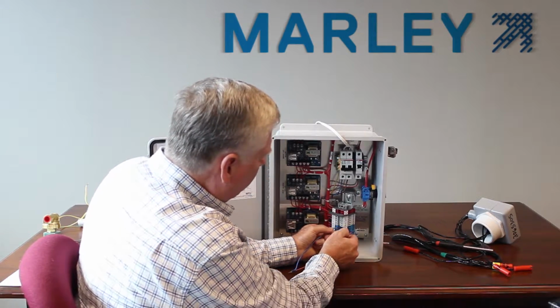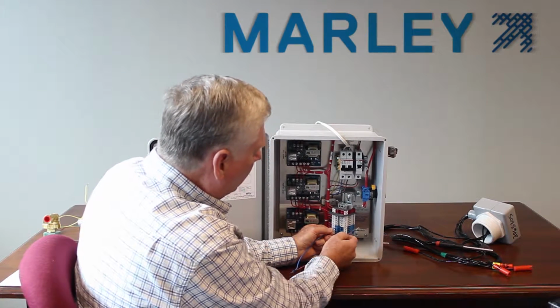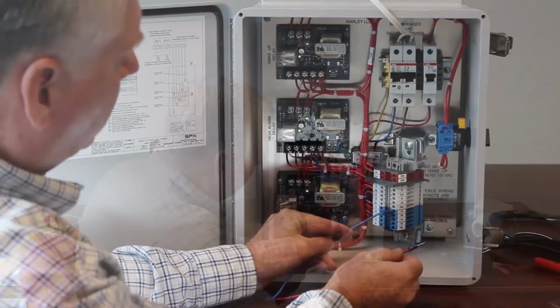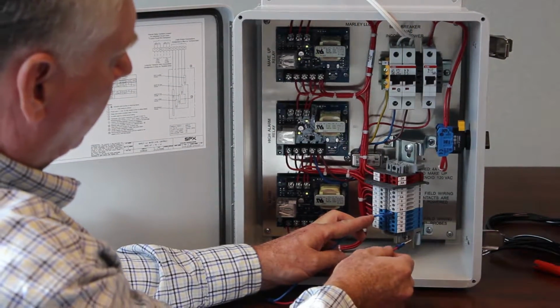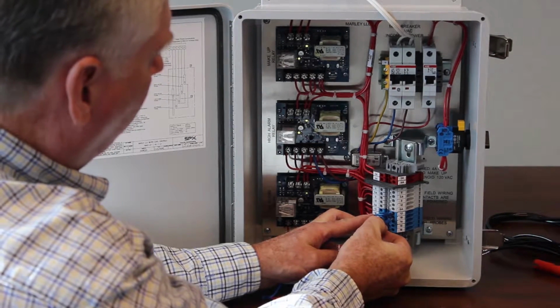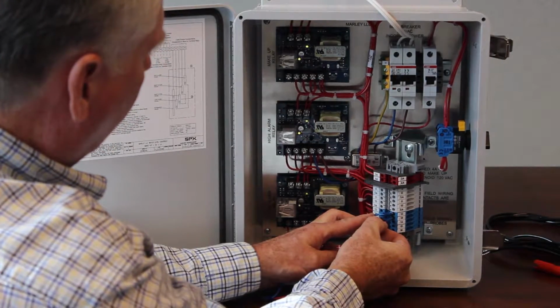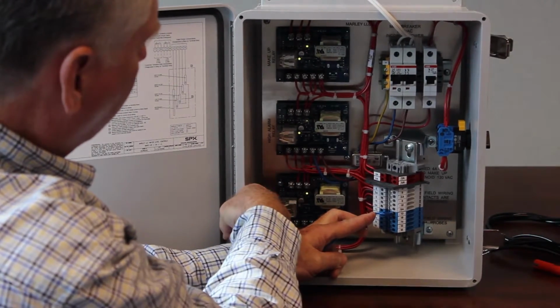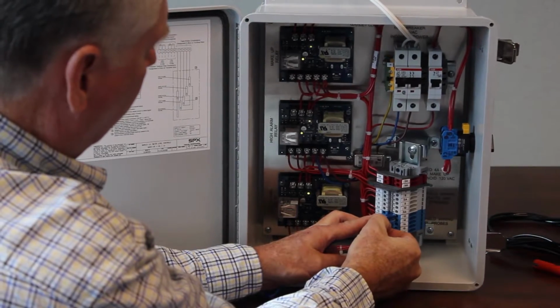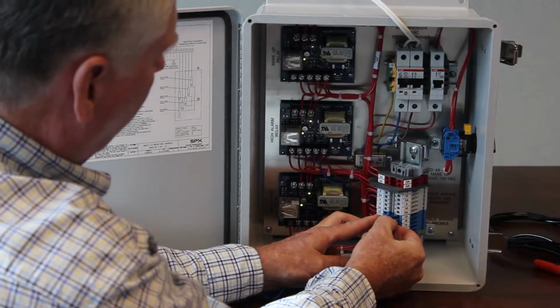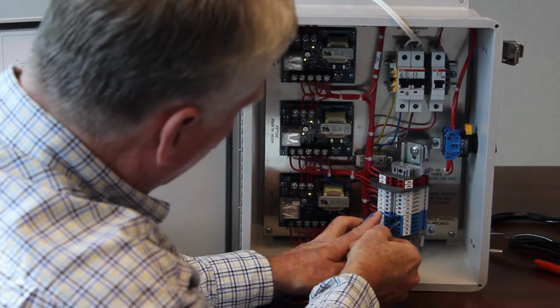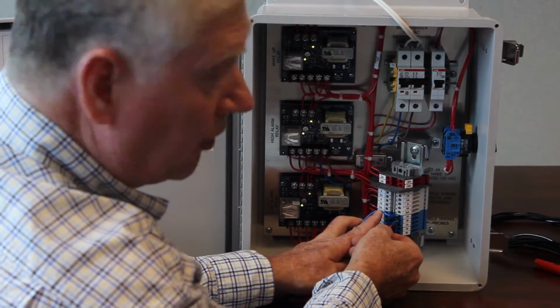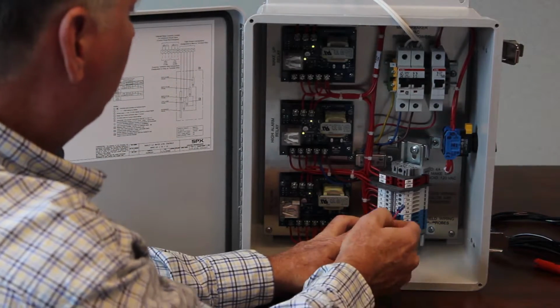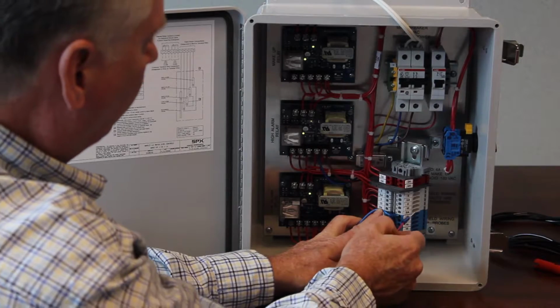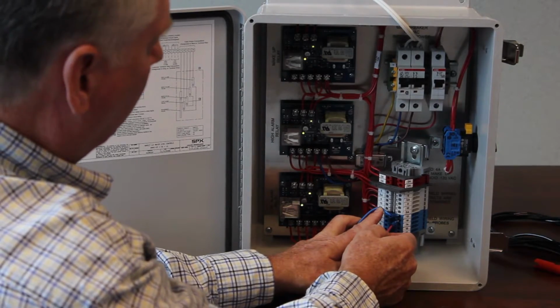So my high alarm card is number 18, I believe. We'll find out here in a second. Through the wire, I'm going to conduct from the reference probe, number 13, and complete the circuit to number 18 probe, and you can see the relay right inside this yellow case right here. You see the relay contacts change state. You can hear it. You can also see this little green light come on, indicating that the card's functioning. So you have 2 visuals and 1 audible. It's hard to hear a relay clicking in the field, but it's nice to have the visuals. Therefore, you know that this card's working.